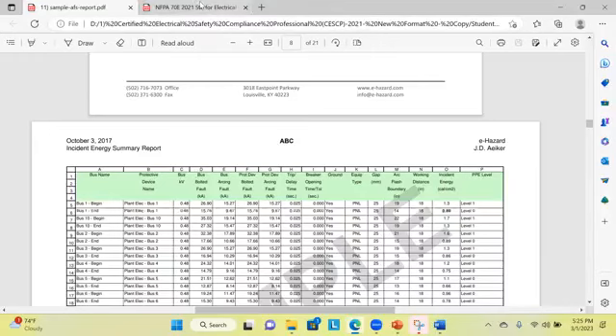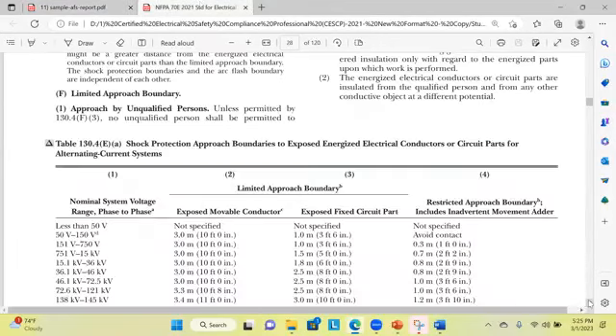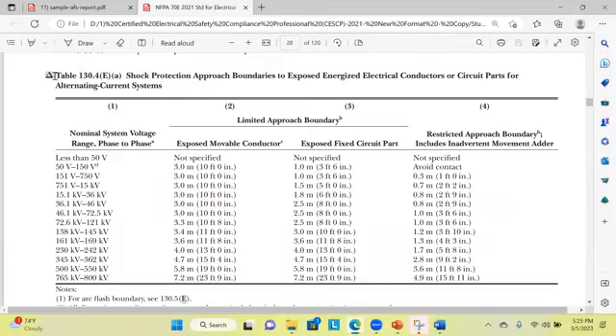How will we develop this shock protection boundary, the limited approach boundary and the restricted approach boundary? We will refer to Table 130.4 E(a), the shock protection approach boundaries to exposed energized electrical conductors or circuit parts, which is given on page number 28 of the standard. You can see that at 50 volts, 70E does not specify the limited approach boundary and the restricted approach boundary. That means up to 50 volts, 70E does not consider that this voltage will result in a shock hazard.